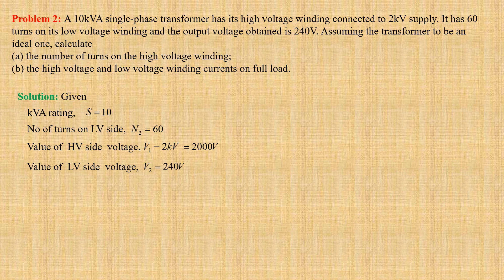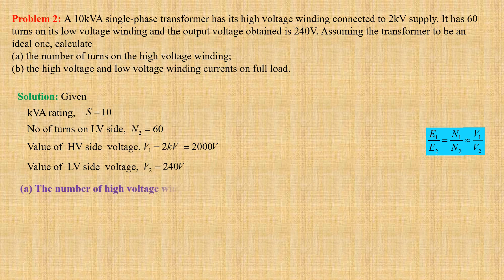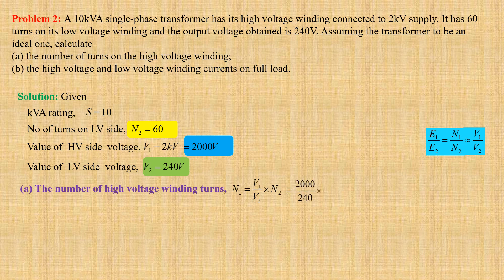For a transformer, E1/E2 equals N1/N2, which is approximately equal to V1/V2. The number of high voltage winding turns N1 equals V1/V2 × N2, that is 2000/240 × 60, which gives us 500 turns.